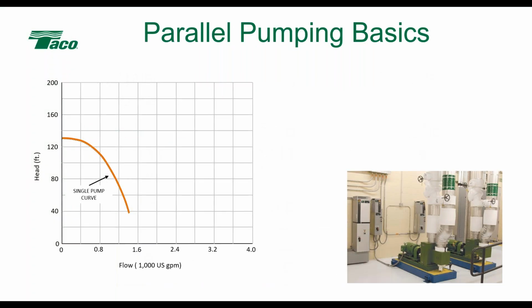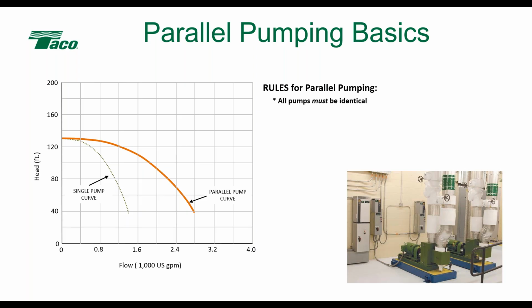So if I look at this, we have to understand a little bit about parallel pumping. In parallel pumping, when I have a parallel pump curve, my flows are additive with both pumps running. The head is whatever the system head is at that design flow rate, but the flows are additive. So that's my design point, and there's my system curve. The thing we have to understand with parallel pumping is that all pumps must be identical. I can't have different size pumps. It's not going to behave well.